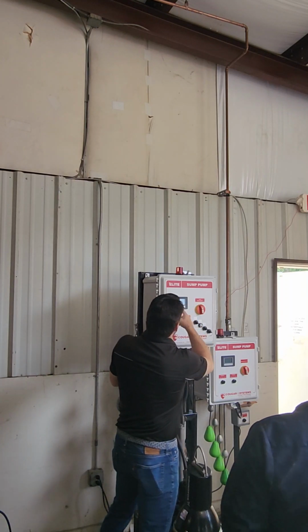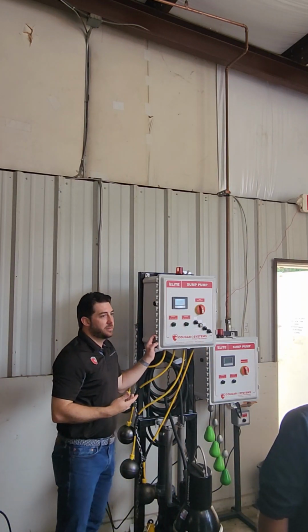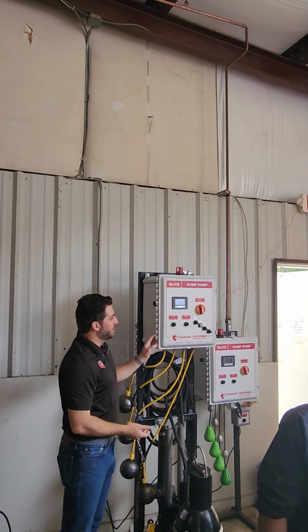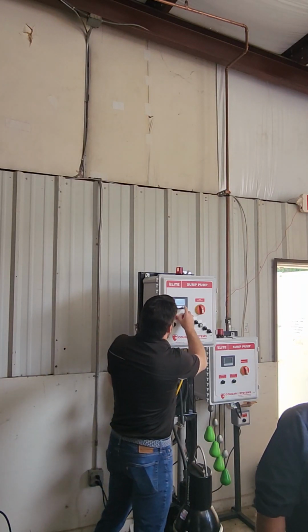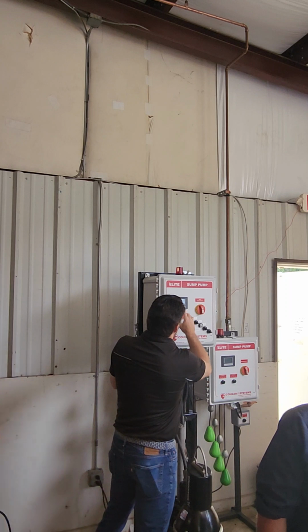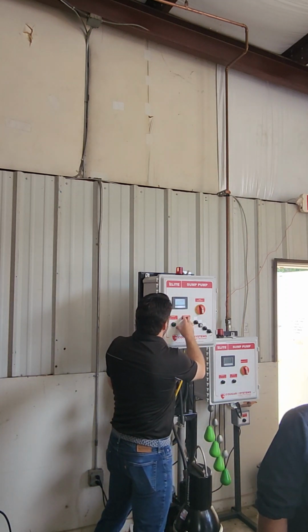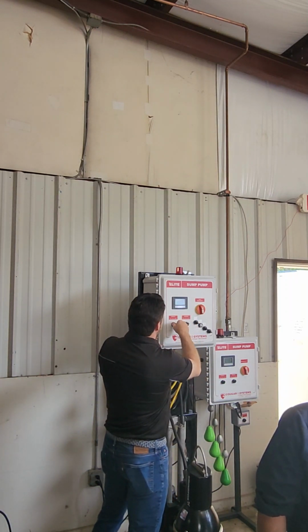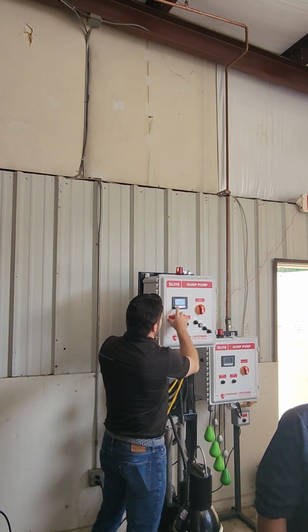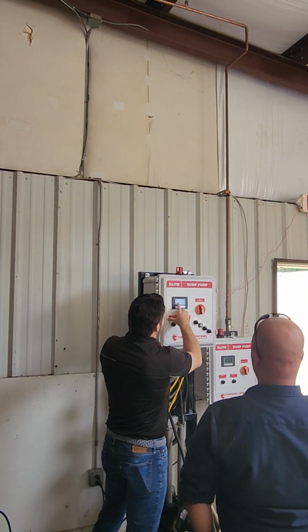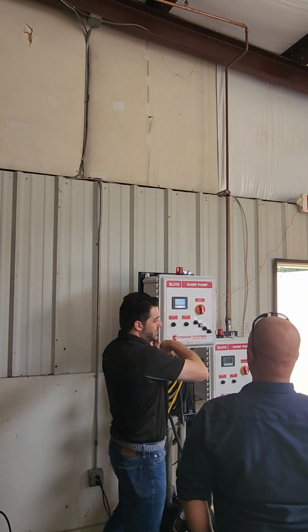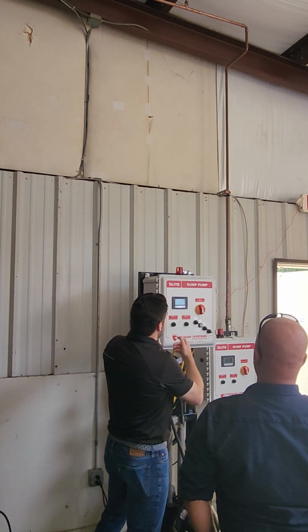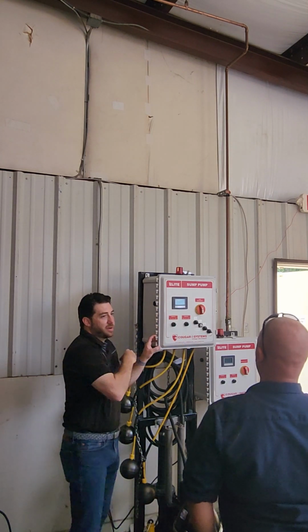And then on the floats, on this one you can adjust between 2, 3, and 4 floats, depending on the application, without having to change anything. And there's different wiring that goes along with that. Okay. So the other thing I'll show you real quick before we jump into everything else is the test screen. So DJ will show you, talk through, testing floats with a voltmeter, but this gives you a way to test them right here on the panel.